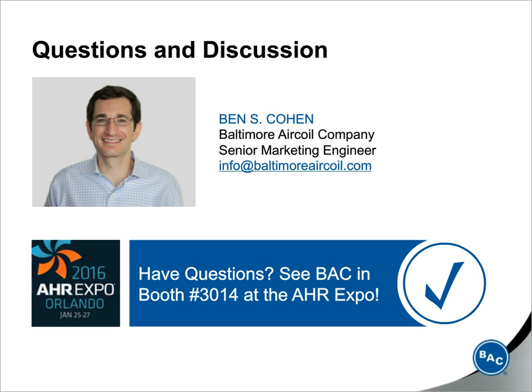If you look at the ASHRAE handbook, the HVAC Applications handbook, in their owning and operating cost chapter, they actually list galvanized steel cooling towers with an estimated service life of 20 years. So by using alternate materials of construction like stainless or tri-armor basins, you can easily extend that way beyond 20 years. Of course, that's all dependent upon whether proper water treatment and maintenance have occurred during that lifespan.